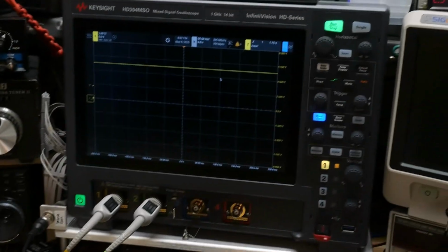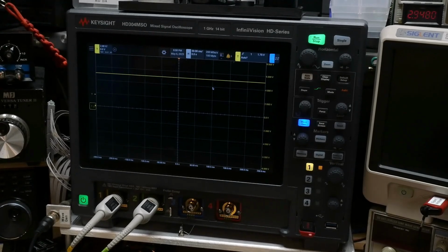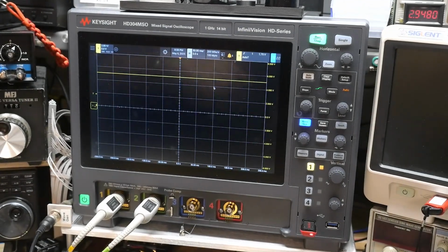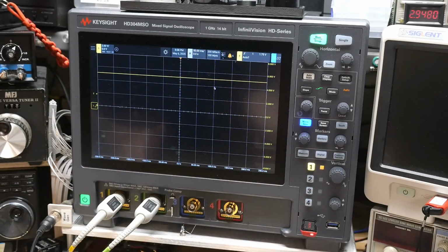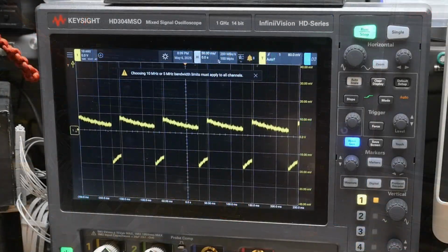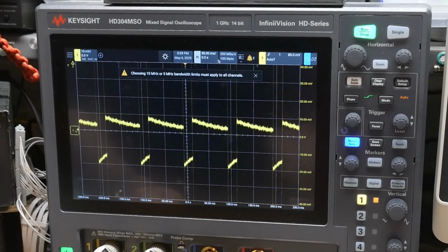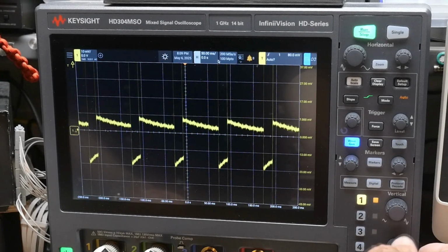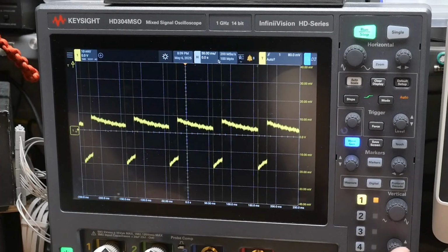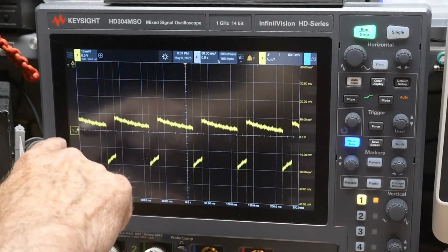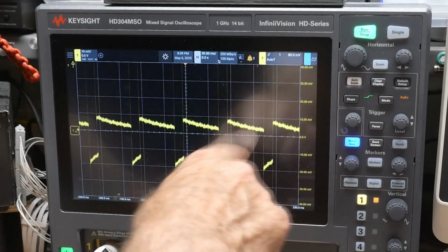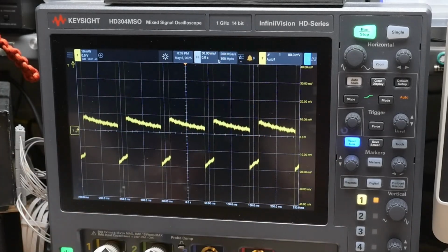And so let's take a look at the voltage rail, okay? So now we'll come up here, and let me readjust the scope here so we can see it better. Okay. So we're here at 5 volts. You can say, hey, everything looks just fine, right? So you say, okay, well, what we normally do is we come here, we do AC coupling. Okay, so we can adjust. If I hit the voltage reference here, it puts it at zero. So we can see that we have some offset in our VCC, right?